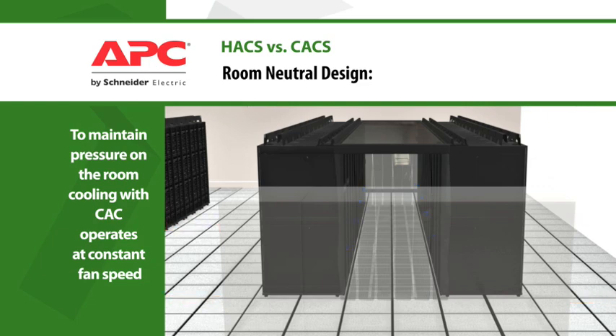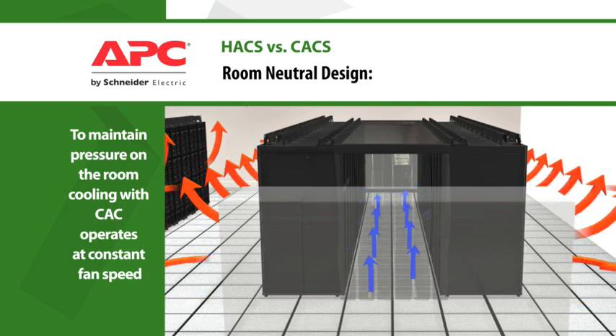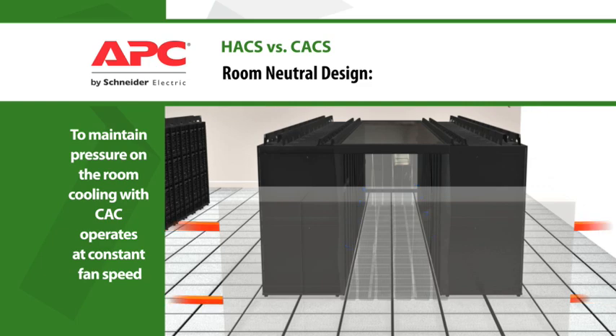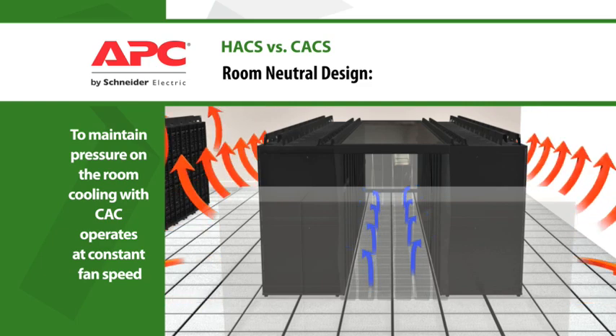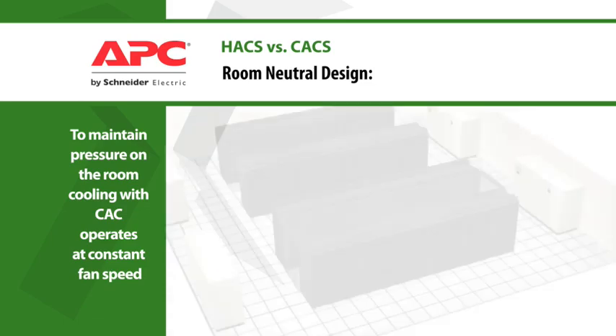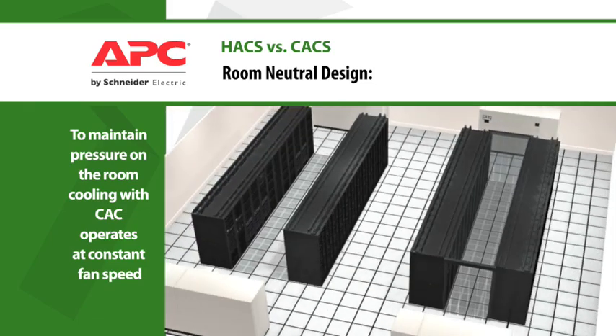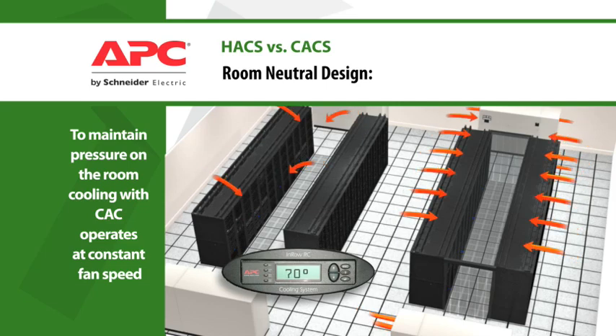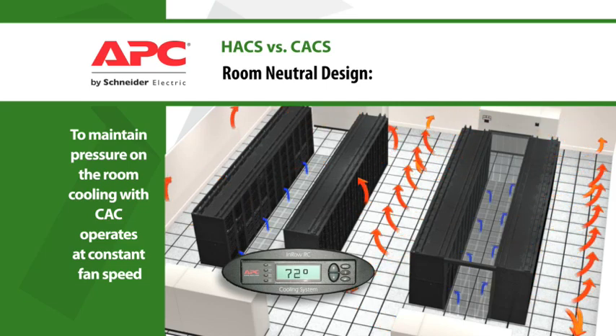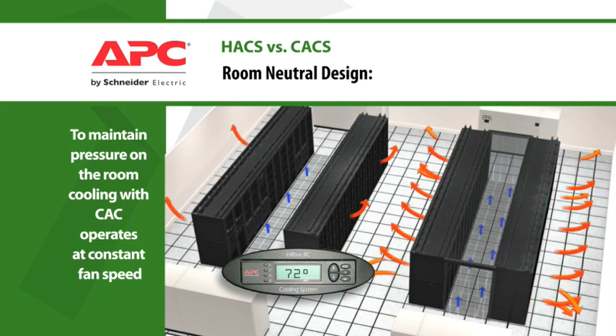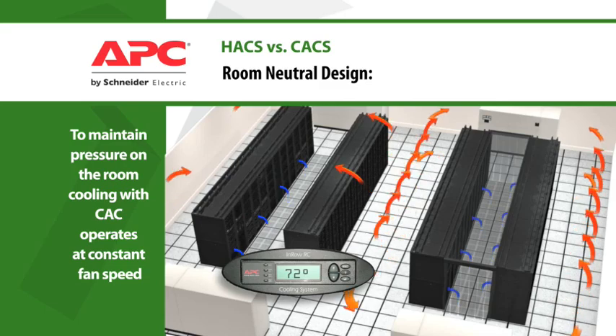The cold aisle containment system is designed to isolate the cold aisle and allow the room temperature to increase, which in turn increases the return air temperature to the room cooling units. Because of floor leakage and other mixing that happens within a room cooling environment, the return air temperature cannot reach the same temperatures as in the HACS, resulting in less efficient operation of the cooling system.